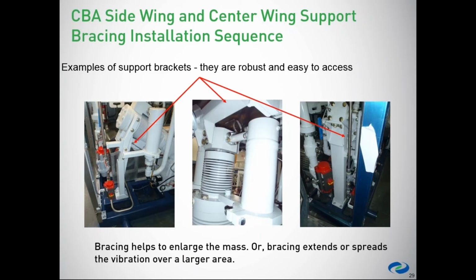This is the center wing support bracing installation. So these are examples of the support brackets, and they're very robust. Basically, what I'm trying to say is that the vibration, if there is any in the compressor, is spread out over a larger area. To me, that means we're enlarging the mass, and others would say that it's just a rigid piece that makes the compressor more rigid. I think we're all right. What it does is reduce the vibration felt immediately at the base of the compressor.